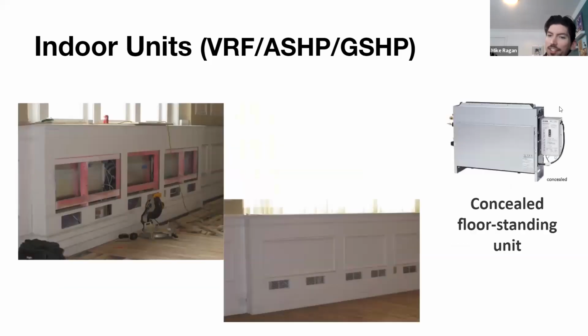Here's an example of exactly that concealed version, just how these are built into the sides. Oftentimes in churches, we have very high ceilings. So putting fan coil equipment at the ceiling level and delivering heat downwards isn't exactly the most efficient way of delivering it to the space. So the best we have to work with is oftentimes the perimeter.